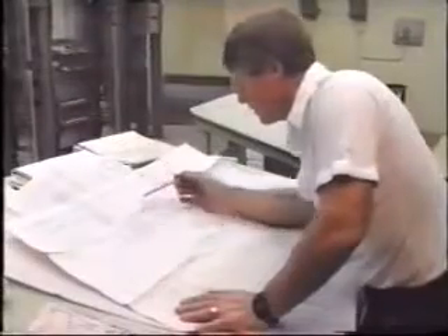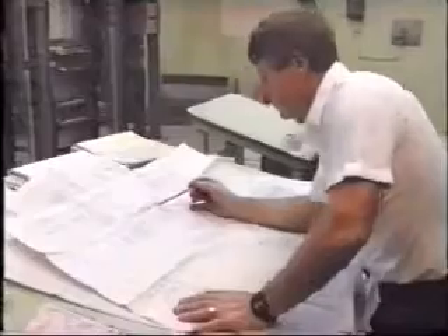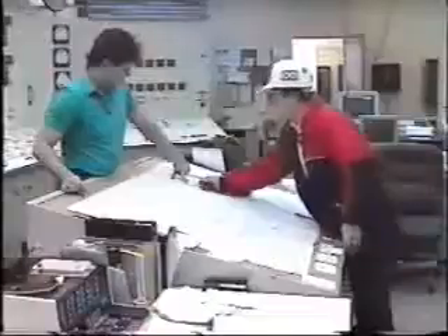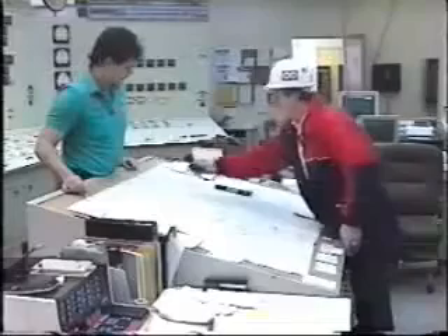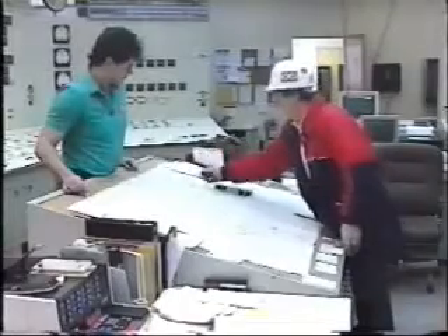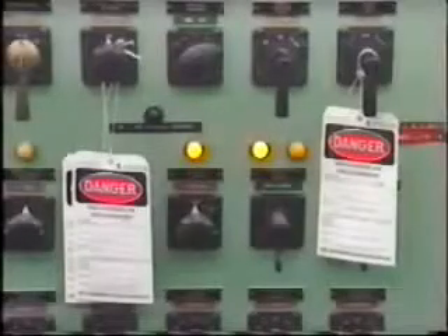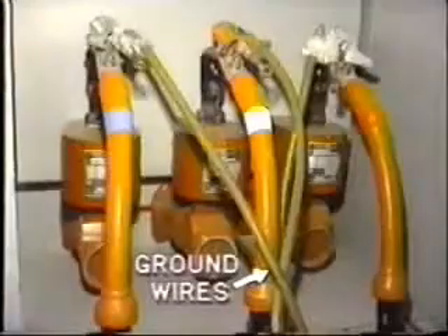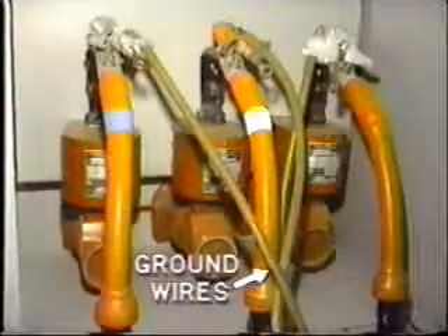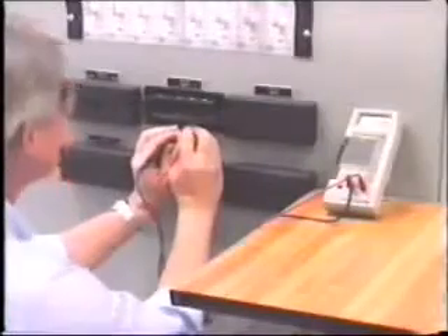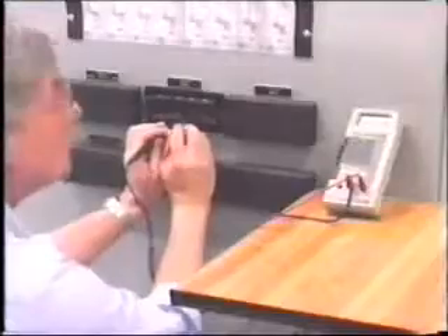Ideally, you should mark up prints to indicate where isolation and grounding is required for safety, and confirm this with the system operator. He may point out that the work area is already isolated and ready for work. You must still check this. Verify that where required, all disconnects are opened, fuses pulled, switches or valves are in the protective position, and all sources of energy are isolated. Has the equipment been adequately grounded? You should always test to ensure that the appropriate circuits are actually dead.